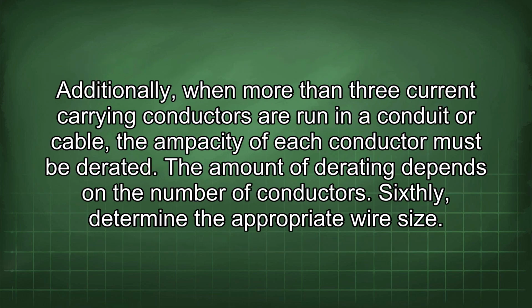Additionally, when more than 3 current carrying conductors are run in a conduit or cable, the ampacity of each conductor must be derated. The amount of derating depends on the number of conductors. Sixthly, determine the appropriate wire size.